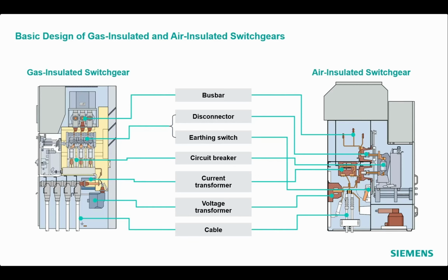Both GIS and AIS use vacuum circuit breakers, whose function, simply put, is to switch operating and fault currents. In case of GIS, the circuit breakers are also present inside the gas compartment. The gas compartment is then sealed for lifetime. In case of AIS, there is the possibility to withdraw the circuit breakers when opening the switching device compartment.